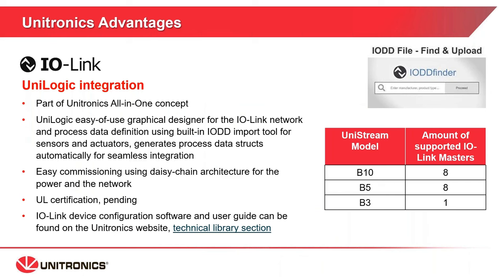As always, we are keeping our all-in-one concept. We developed a very easy setup in UniLogic. We have an IO-DD import tool inside UniLogic. For those less familiar with IO-Link technology, an IO-DD file is a simple XML file provided by the IO-Link device vendor, free to download on their site or from the IO-DD finder site. This file contains all the details of the information available from the device, such as identity, parameters, process data PDOs, diagnostic data, and communication protocols. I will show you that later in the UniLogic demo.